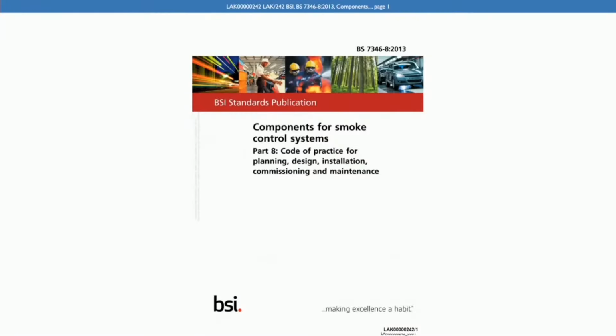This is a British standard called Components for Smoke Control Systems, and it's titled A Code of Practice for Planning, Design, Installation, Commissioning and Maintenance. And you can take it from me that the Smoke Control Association guide refers primarily to this British standard as the recognised code of practice for commissioning and acceptance testing of smoke control systems. Now, were you familiar with this British standard as well?